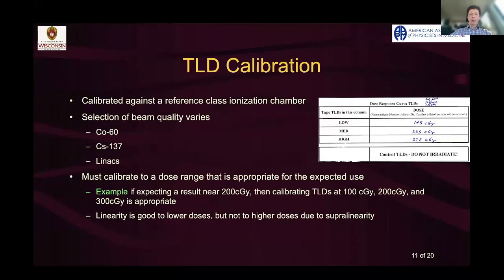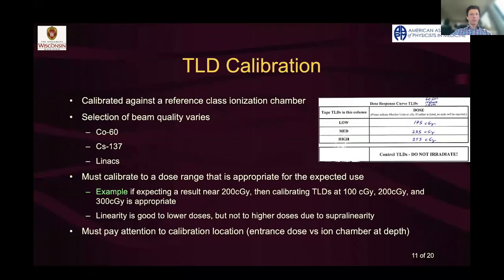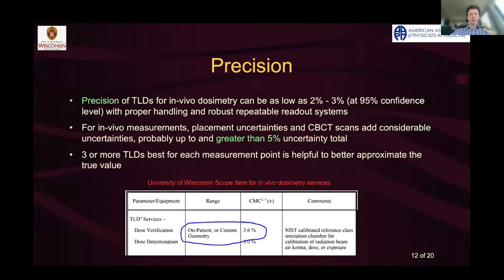So this is just a picture of one of our forms where someone is irradiating a low, a medium, and a high TLD, and you send these in along with the control TLDs. You need to pay attention to the location of the calibration, so the entrance dose versus the ion chamber depth. You don't necessarily want to just place the TLDs right on the entrance if you've determined the dose at Dmax or a deeper depth. So you'd like to keep those two consistent when you irradiate your calibration TLDs.